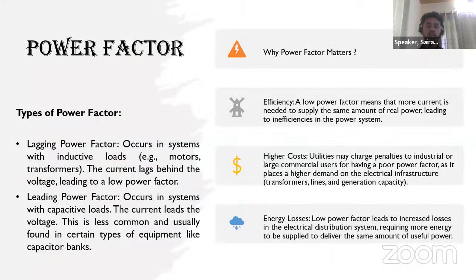Then there are two categories of power factor: lagging power factor and leading power factor. Lagging power factor usually comes with inductive loads, the motors and transformers, in which the current lags behind the voltage. That is considered the low power factor. Leading power factor is for capacitive loads, like capacitor banks, which are helpful in bringing the power factor back to unity.